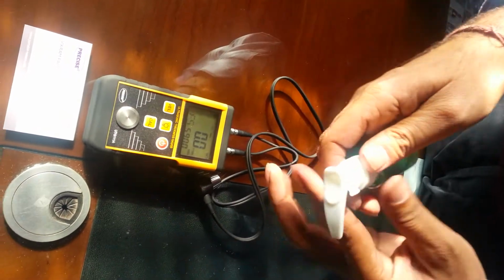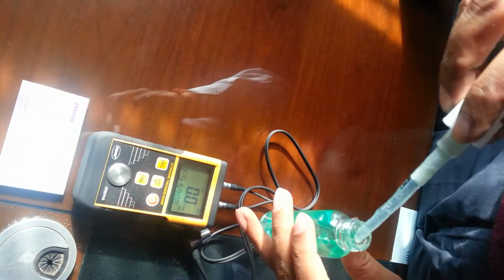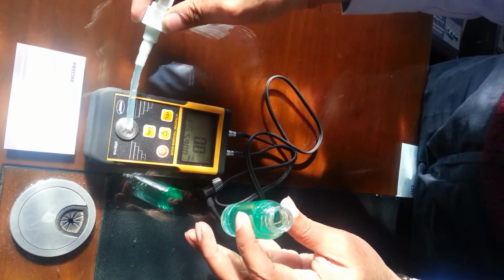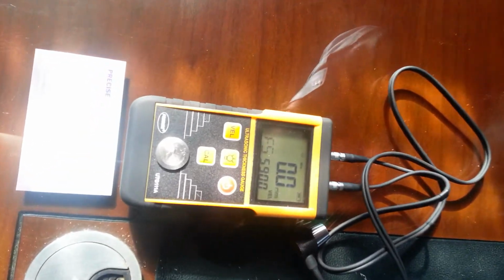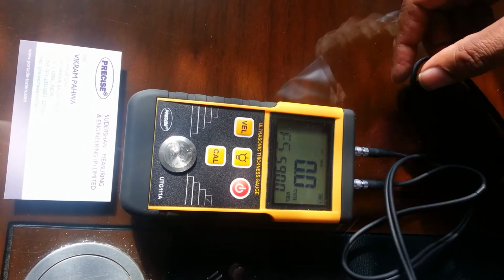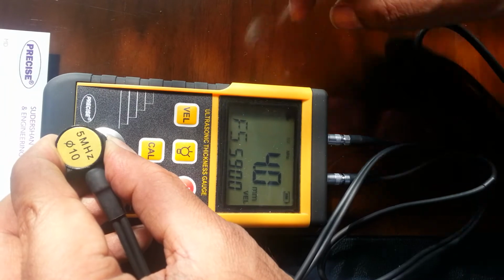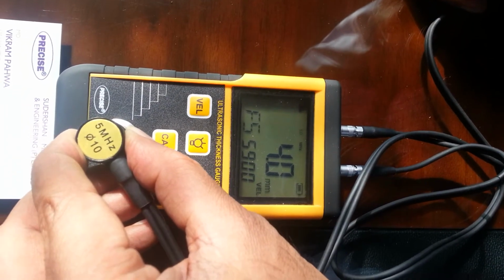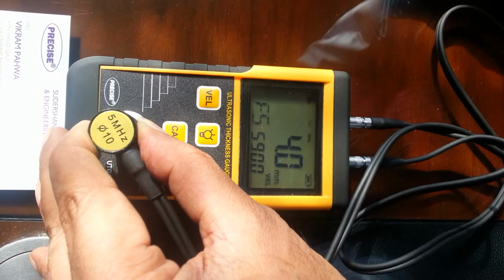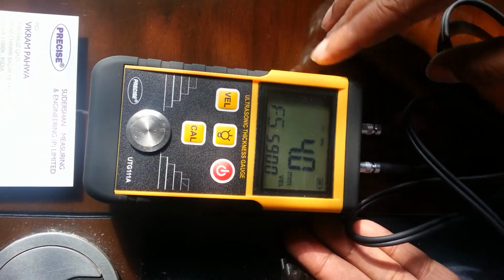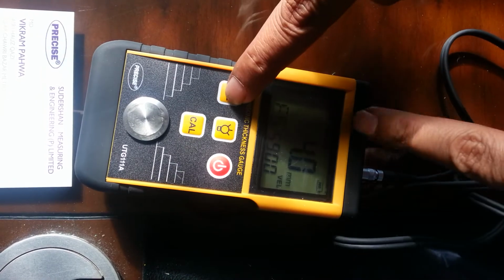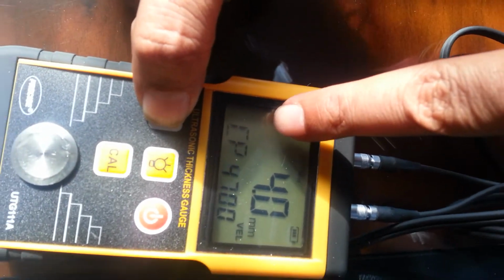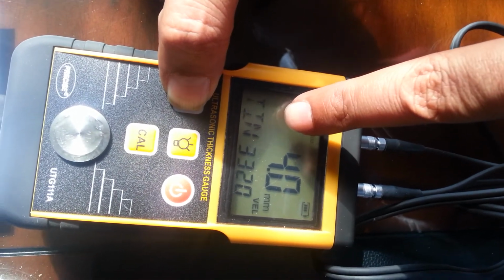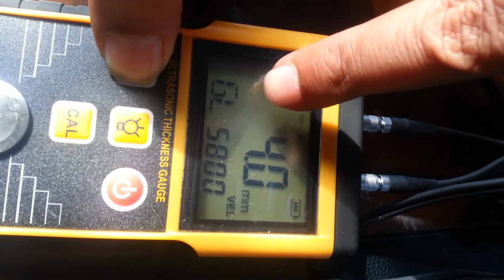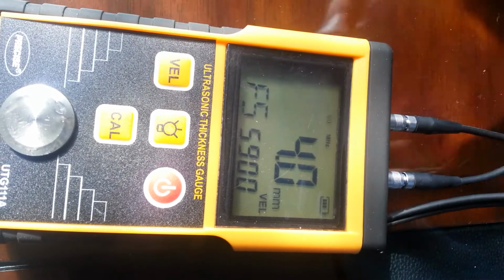First thing is to check the calibration. The internal calibration is 4 millimeters. We use coupling gel so that there is no gap or bubble and we are able to get the right reading. It should show us a reading of 4. So here we see it is giving us a reading of 4, which means this particular machine is good and ready for use. Now if our material is iron and steel, we can directly use it, else we change to aluminium. It's a toggle, so aluminium, copper, brass, zinc, tin, lead, and so on. So we come back to iron and steel. This is how it works, and it's very simple to use.